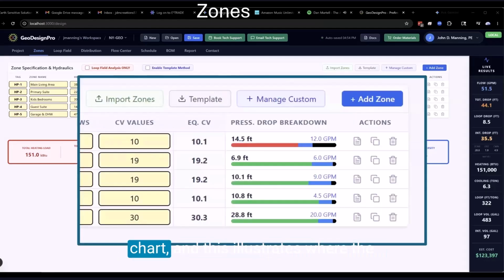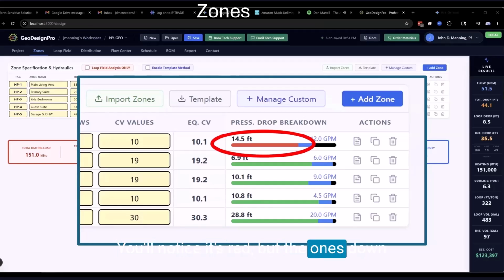Now I'm going to blow up that little color chart, and this illustrates where the pressure drop is occurring in that circuit. The first part is the heat pump. And you'll notice it's red, but the ones down below are green. And it's just a tickler. It's telling you that maybe the pressure drop of your devices, the piping, the valve you chose, is too big. Those are items you have control of. The color will change when you get the pressure drop of the heat pump to be at least 70% of that circuit. You're not going to be able to change the pressure drop of the heat pump, but you can change the piping diameter, perhaps, the CV of a two-way valve.